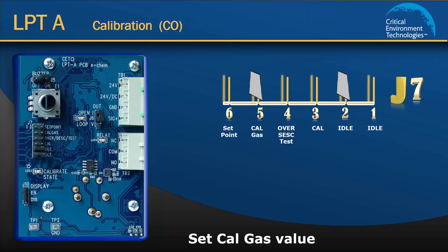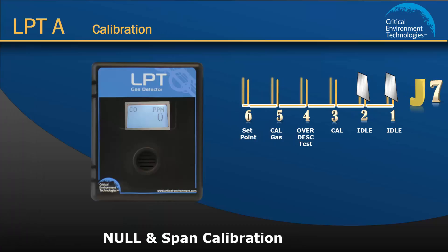To complete the set cal gas value procedure, move the cal gas jumper back to the idle position. The LPTA offers one jumper calibration, meaning you don't have to move jumpers back and forth to different positions when doing the null and span calibrations. The jumper is moved once and remains in the cal position until both calibration procedures are complete.